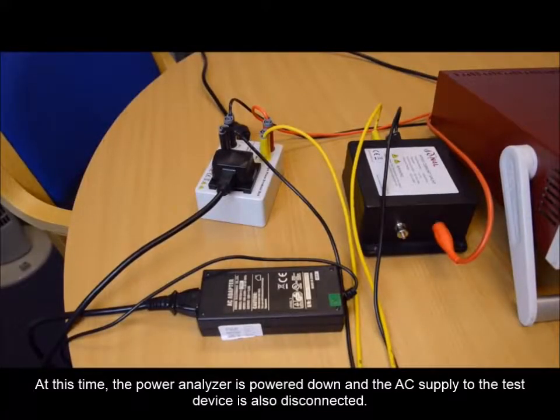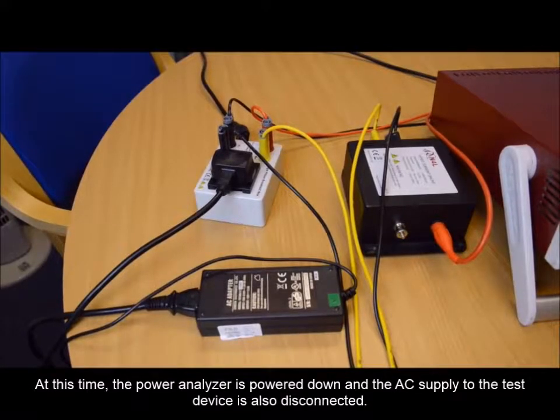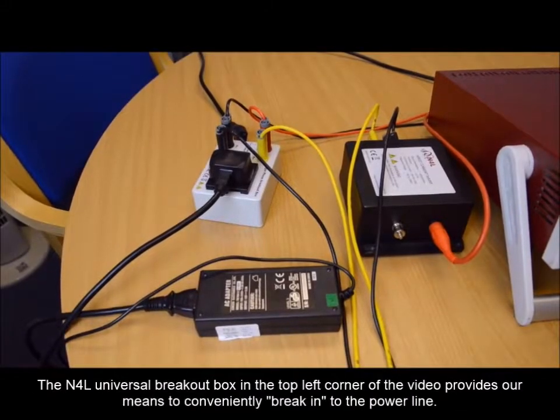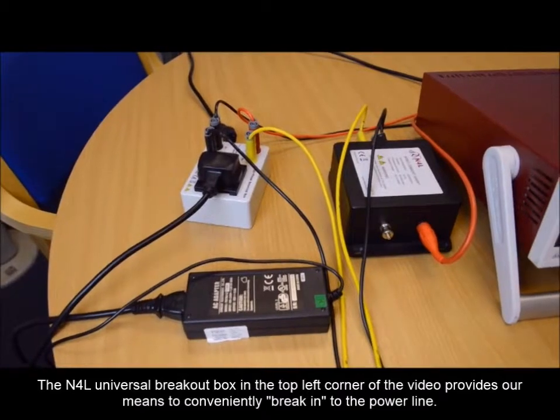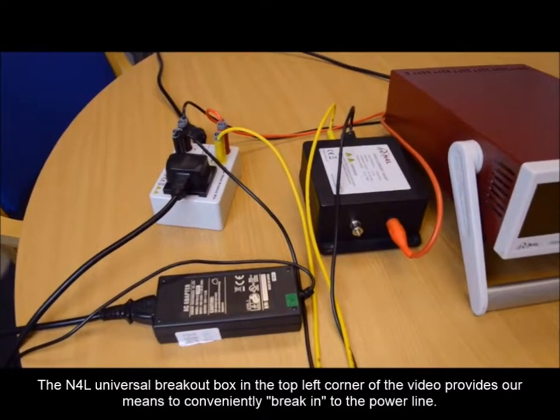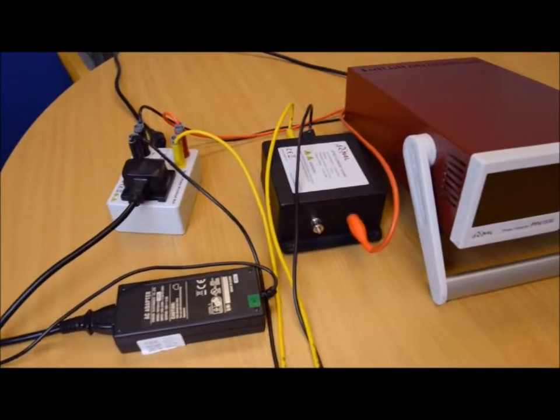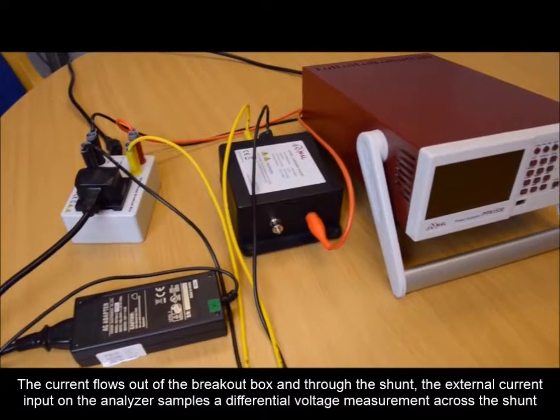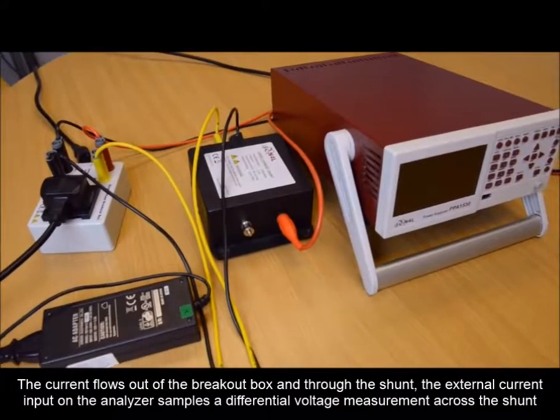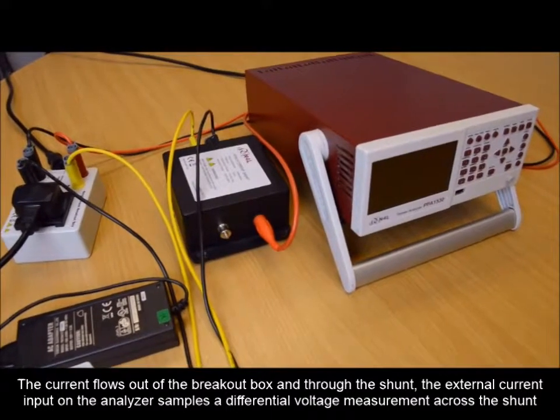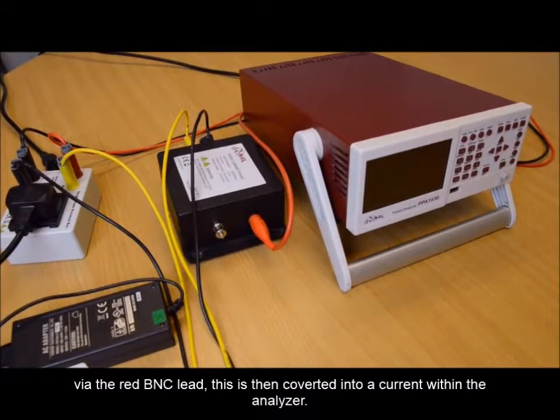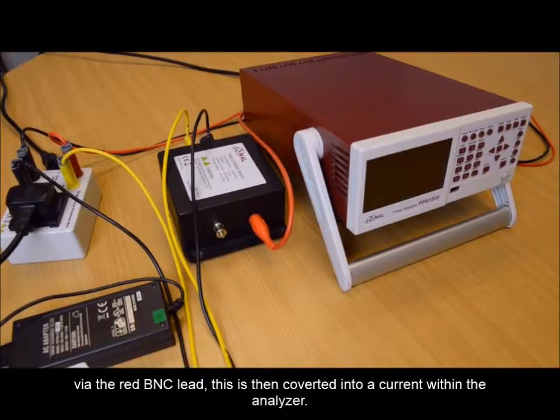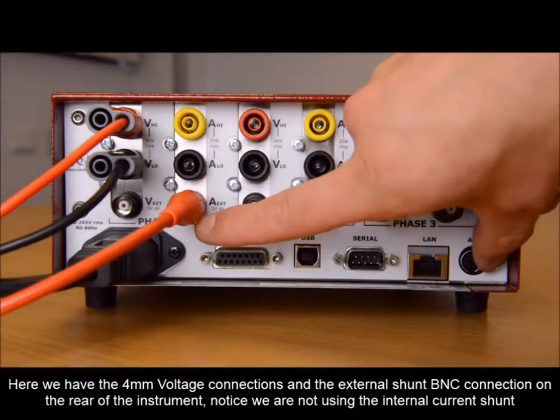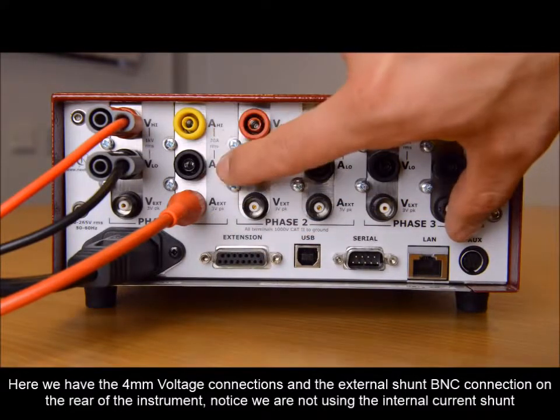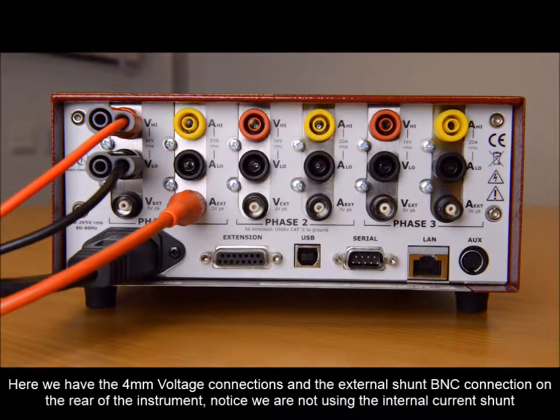At this time, the power analyzer is powered down and the AC supply to the test device is also disconnected. The universal breakout box in the top left corner of the video provides our means to conveniently break into the power line. The current flows out of the breakout box and through the shunt. The external current input on the analyzer samples a differential voltage measurement across the shunt via the red BNC lead. This is then converted into a current within the analyzer. Here we have the 4mm voltage connections and the external shunt BNC connection on the rear of the instrument. Notice we are not using the internal current shunt.